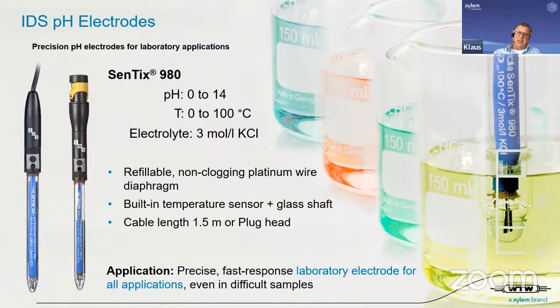This is a fast responding electrode, very fast responding, and it will also be insensitive against stirring effects. So this is an electrode which you can use in almost any laboratory application. Also Tris buffers and all that stuff which normally causes problems for electrodes which have a ceramic diaphragm. This kind of diaphragm does usually not clog and will guarantee a fast and secure measurement. The temperature range is seldom used, of course, but goes up to 100 degrees. So this is one of the most sold standard electrodes in the laboratory business of our company.